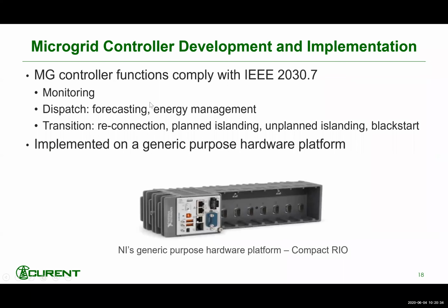And the second major task is controller development and implementation. Here the controller development complies with the standard IEEE 2030.7, which specifies the microgrid control functions, including the basic monitoring function and the dispatch.